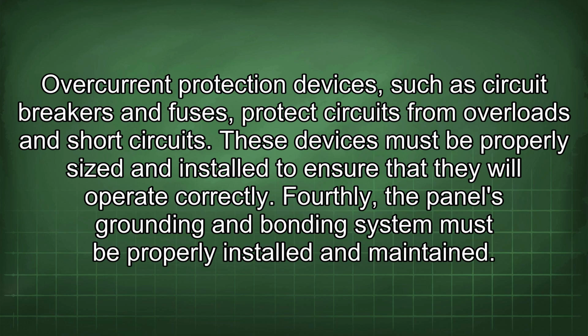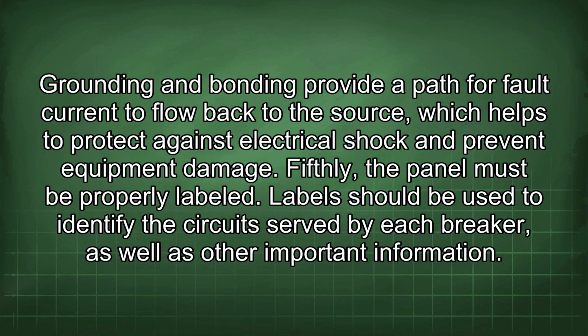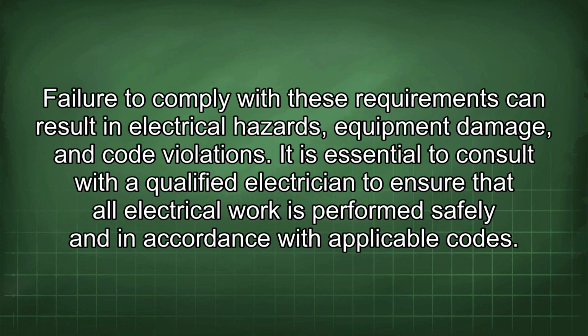Fourthly, the panel's grounding and bonding system must be properly installed and maintained. Grounding and bonding provide a path for fault current to flow back to the source, which helps to protect against electrical shock and prevent equipment damage. Fifthly, the panel must be properly labeled. Labels should be used to identify the circuits served by each breaker, as well as other important information. Failure to comply with these requirements can result in electrical hazards, equipment damage, and code violations. It is essential to consult with a qualified electrician to ensure that all electrical work is performed safely and in accordance with applicable codes.